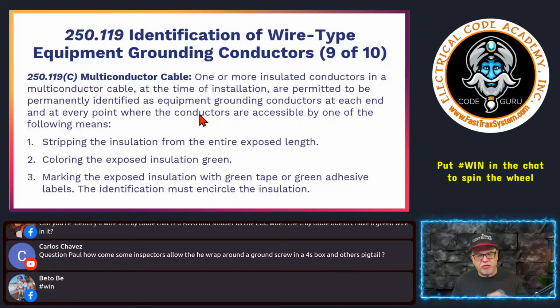All right, so I'm going to answer the questions that people have been asking. Now, what about 250.119(C)? What if we have multi-conductor cables? It says, if you have one or more insulated conductors in a multi-conductor cable, which you would, you're going to have more than one, by the way, at the time of installation they are permitted to be permanently identified as an equipment grounding conductor at each end and at every point where the conductors are accessible by one of the following means. So this is a multi-conductor cable, allowing you to re-identify inside of a cable assembly, not size specific.